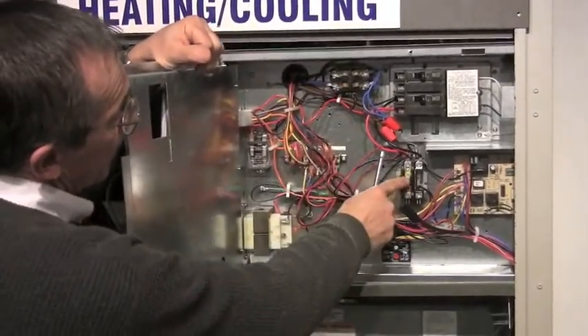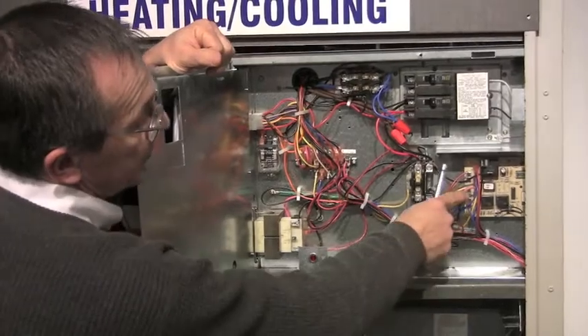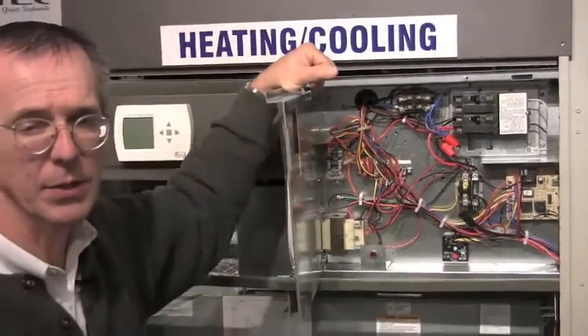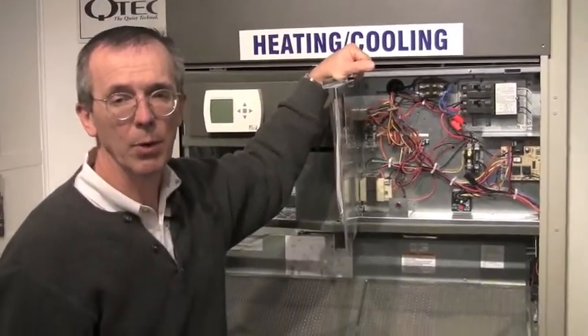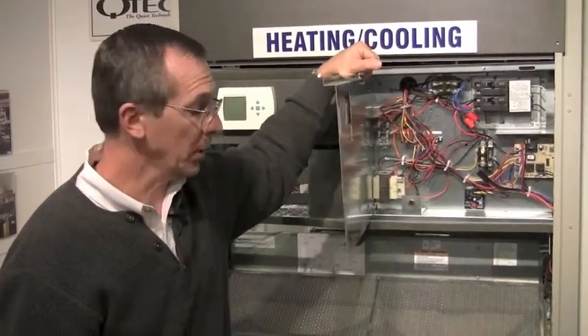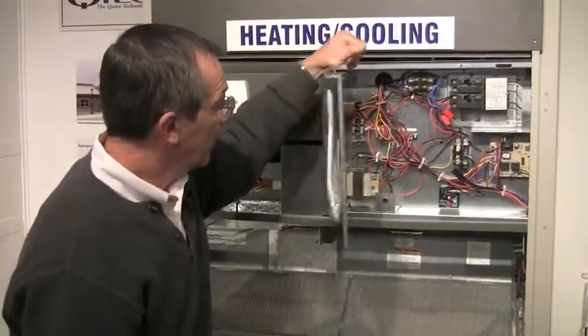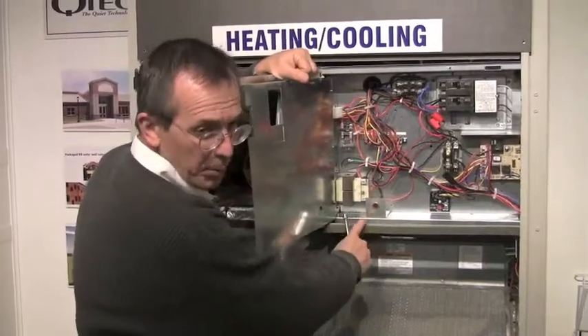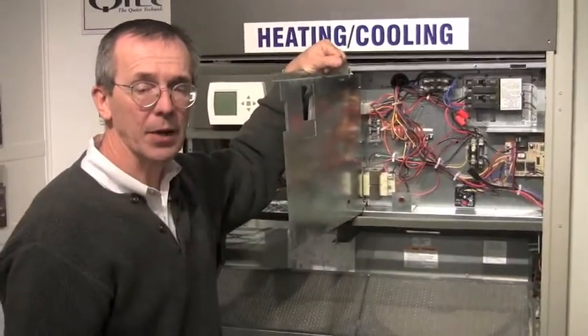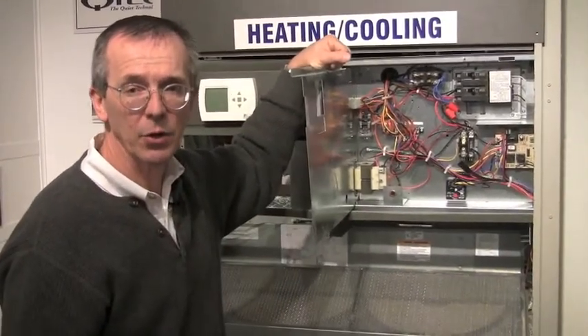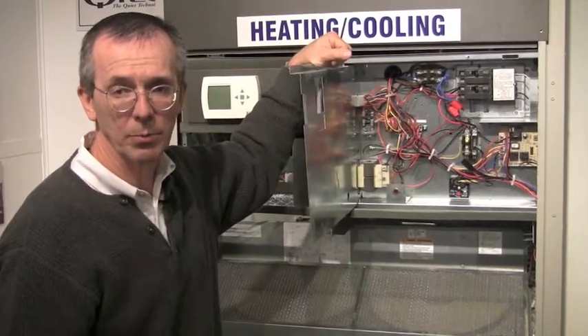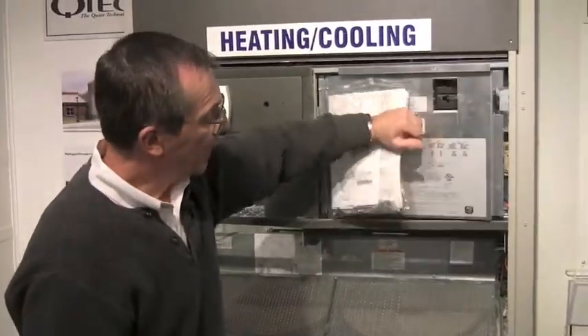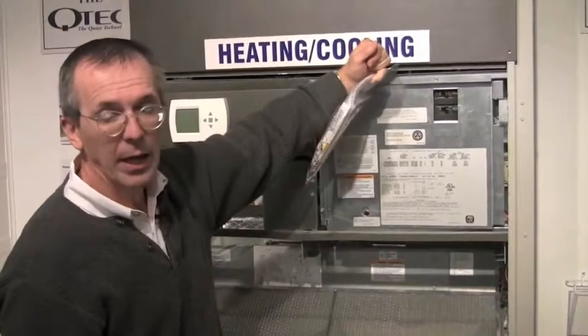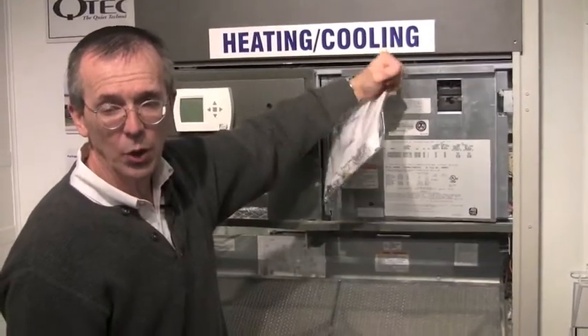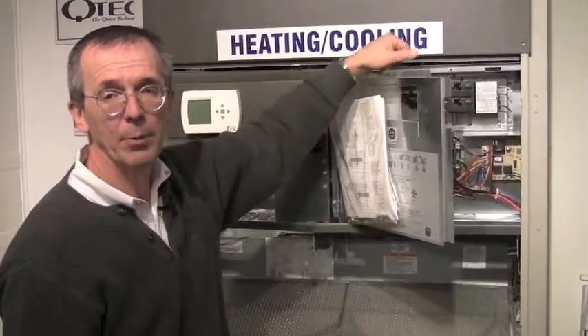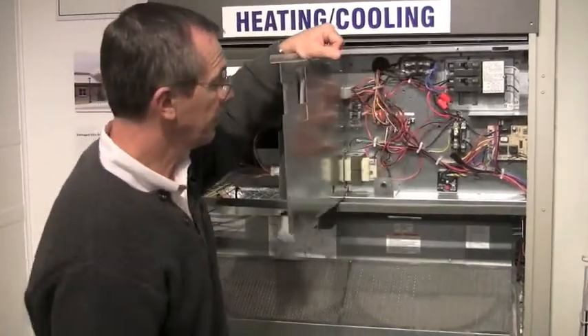Electric heat contactor, compressor contactor, heat pump control board. This is the same board that has been installed in Bard wall mounts for many, many years. This is a high pressure and a low pressure switch light. Down in the compressor section, standard on the Q-Tec is a high pressure switch and low pressure switch. If you have a service call on the unit, and if that light is on, you will know that the unit has tripped on high pressure or low pressure.